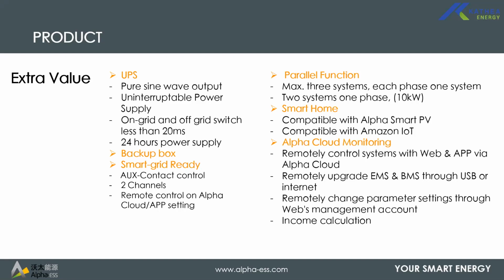There is a backup box for our region. It's not yet certified, but it's something in the pipeline. I'm not sure on the specifics of when it would be deployed, but it's in the pipeline. With the backup box, you can set your battery to supply certain circuits up to specified battery SOC levels. And then the system offers auxiliary contacts, 2 channels, which you can use to control your external devices, switch on your generators or other relays and so forth. So those are digital inputs.